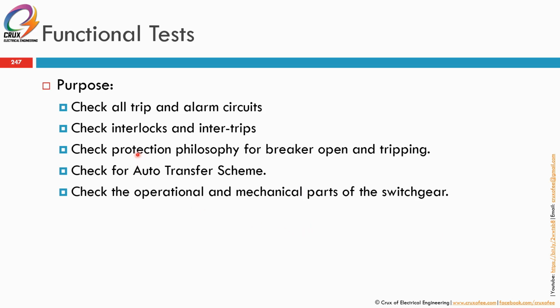Then we also have a functional test. So the purpose is to check all trips and alarm circuits, to check all the interlocks and intertrips from upstream, downstream to upstream, and check the protection philosophy for the breaker open and tripping. For example, if you are having this philosophy of two incomers normally open and a bus section normally closed, or two incomers normally closed and bus section normally open, you would like to test the changeover or the auto transfer scheme to make sure that it works as per your philosophy, and also check for auto transfer scheme.